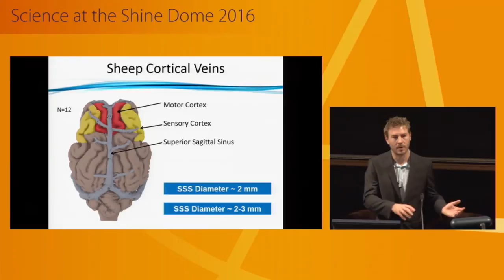So the device itself, we've called it a stentrode. It's a self-expanding electrode array. You can see in the image that we deliver it through a less than 1 millimeter catheter to the area of interest, and when we're there, we can remove the catheter and the device just self-expands and presses the electrodes against the vessel wall. Now, this is important. Obviously, it's very hard to get a 4mm device through all the way, so being able to have this self-expansion is very important. But also, by using the stent technology, we can ensure that the inside of the stent and the inside of the vessel doesn't have anything in it. It expands and all the electrodes are on the vessel wall around the outside, and blood can still flow through the middle, so we're not causing any issues there.